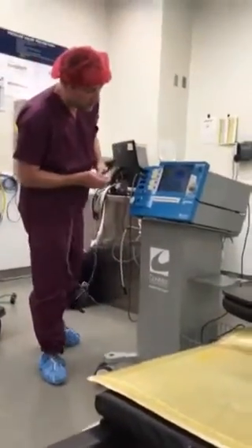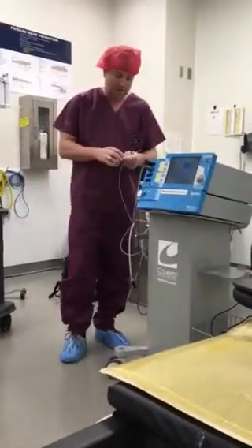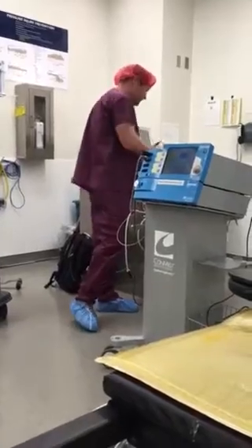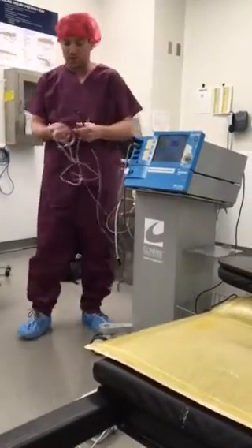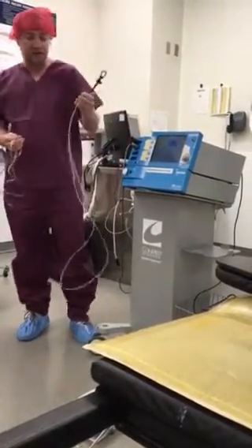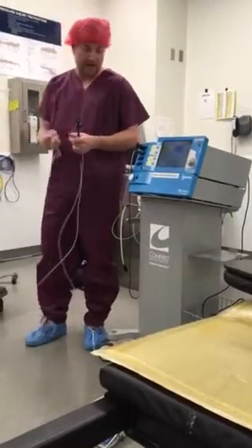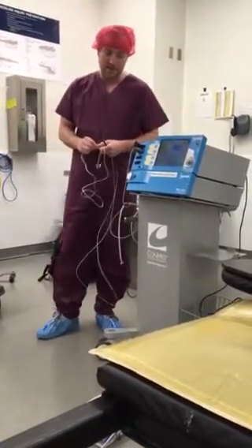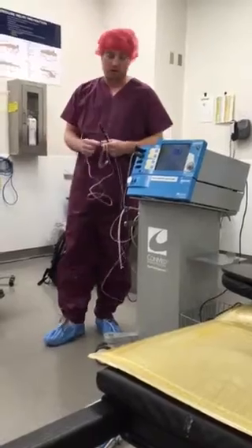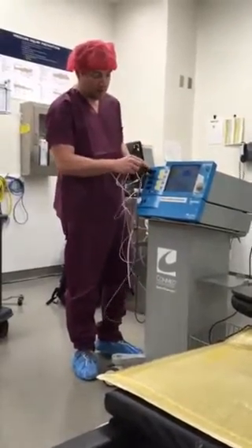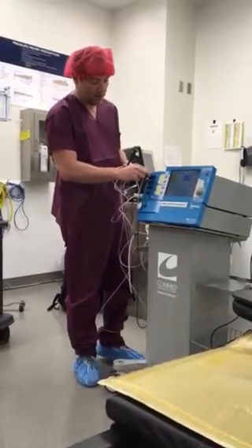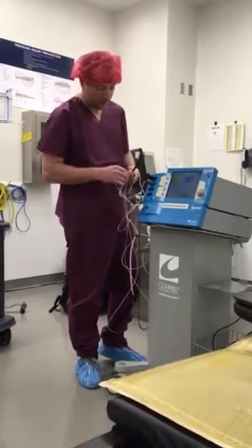When you turn it on, you just want it to go to argon beam snare. The argon beam snare means it's going to be set up for this exact device. There's two parts to it, come in little separate bags. One is the actual probe itself, one is the gas line. Because this is hooked in both cautery and gas up to it, you need both. You need one connection going from the cautery portion, one connection going from the gas portion.